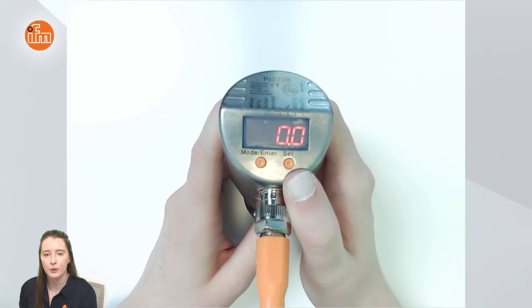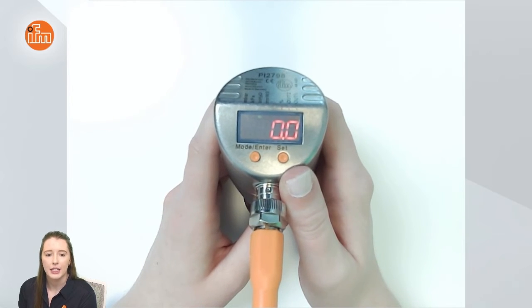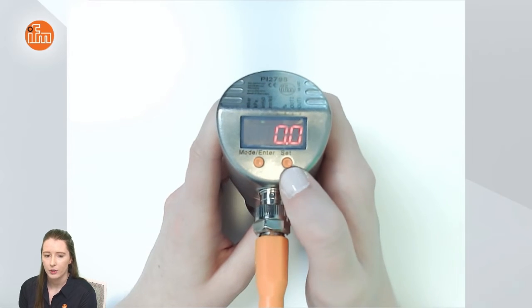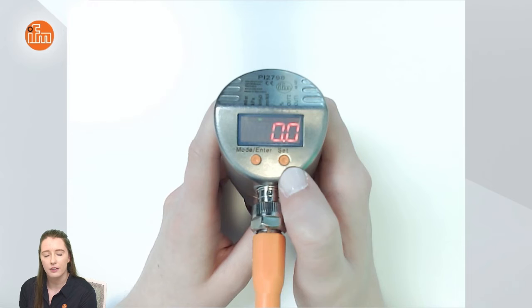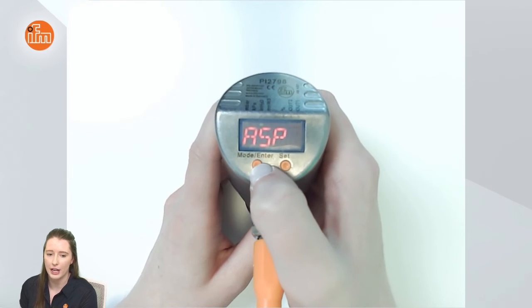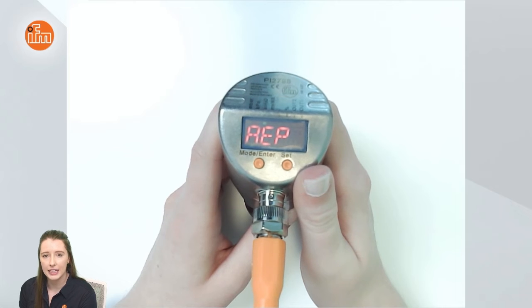It is factory set for zero meaning your four milliamp output would be representing zero inches of water column. Again you would change this by holding down the set button and then when you're at the value you want to set it for you'd press mode enter and then if you press mode enter again you'll see aep for analog endpoint.